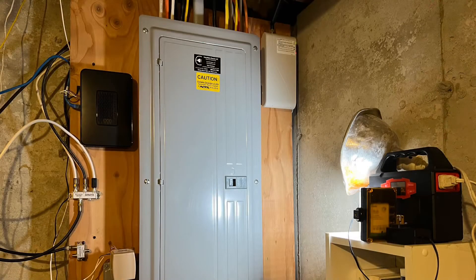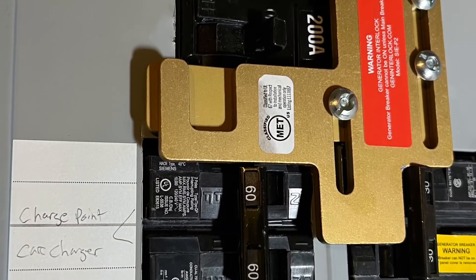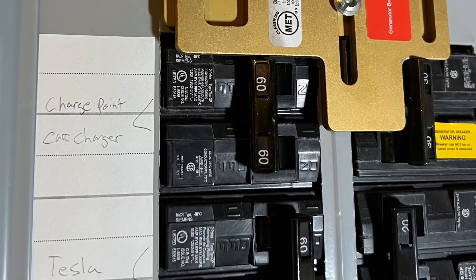The first thing I had to do is upgrade my panel. This house had a 100 amp service, and all the breaker slots were full, so I had to upgrade to a 200 amp panel. It wasn't a cheap proposition — about $2,000. The electrician installed the 200 amp breaker with a generator interlock, and then two 60 amp breakers: one for the charge point and one for the Tesla charger.